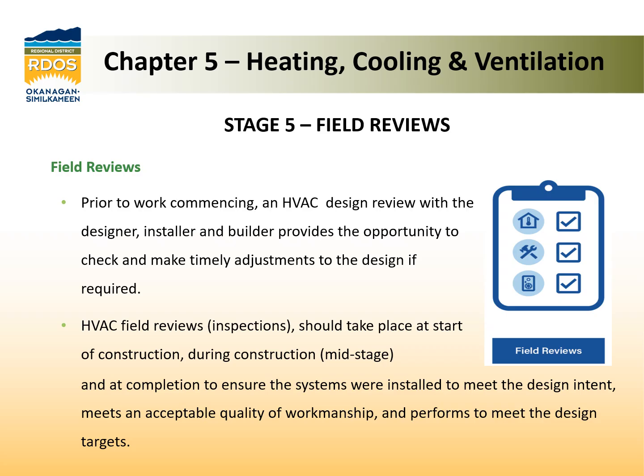A field review before cover with drywall is critical. Basically, this is an inspection. Was the design followed or not? Is the workmanship acceptable or not? Are there any deficiencies that need to be corrected before cover? And finally, before occupancy, another inspection to check the system function against design targets and ensure that a full commissioning was completed.